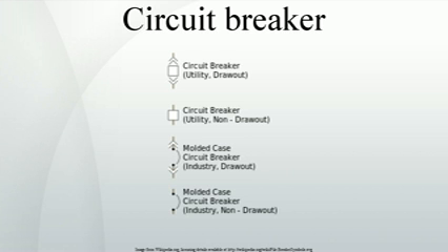Magnetic circuit breakers. Magnetic circuit breakers use a solenoid, electromagnet, whose pulling force increases with the current. Certain designs utilize electromagnetic forces in addition to those of the solenoid. The circuit breaker contacts are held closed by a latch. As the current in the solenoid increases beyond the rating of the circuit breaker, the solenoid's pull releases the latch, which lets the contacts open by spring action.